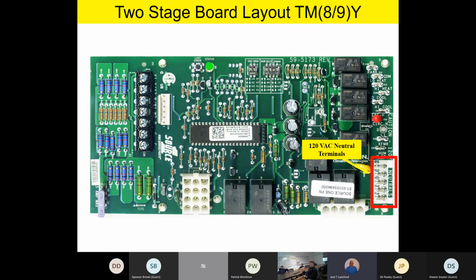You get the idea. So that neutral bus, they're all tied together electrically, and so it doesn't matter which terminal you use because they're all just tied together. If you look at the back of the board, there's just a solid piece of metal back there for those neutral terminal bus. As we come along the bottom of the board, we'll notice there's an output harness to the hot surface igniter, the HSI, and the inducer fan motor.